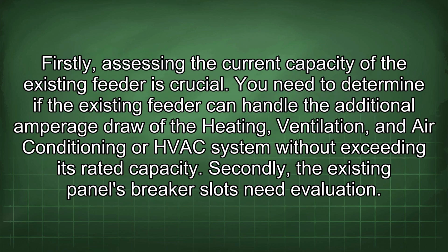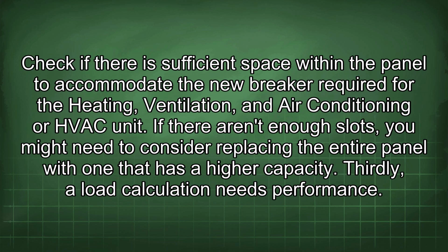Firstly, assessing the current capacity of the existing feeder is crucial. You need to determine if the existing feeder can handle the additional amperage draw of the heating, ventilation, and air conditioning, or HVAC, system without exceeding its rated capacity. Secondly, the existing panel's breaker slots need evaluation. Check if there is sufficient space within the panel to accommodate the new breaker required for the heating, ventilation, and air conditioning, or HVAC, unit.